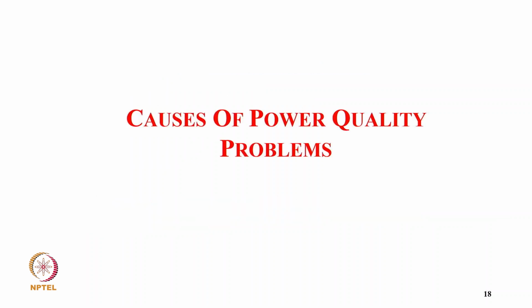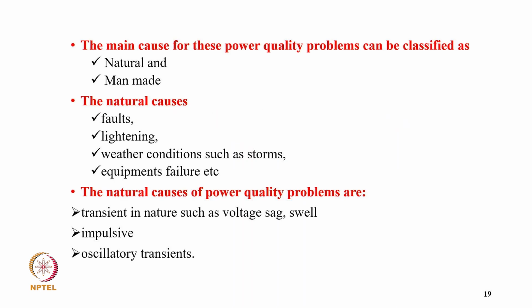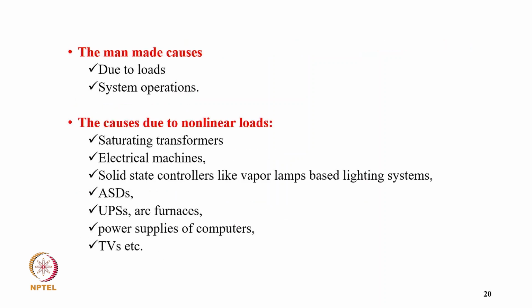Now coming to causes of power quality problems. The main causes can be classified as natural and man-made. The natural causes are fault, lightning, weather conditions such as storms, equipment failure, etc. The natural causes of power quality problems are transient in nature, such as voltage sag, swell, impulsive, and oscillating transients. And the man-made causes are due to loads and system operations, and the cause is due to nonlinear loads: saturating transformers, electrical machines, solid state control like vapor lamps, lighting systems, adjustable speed drives, UPS, arc furnaces, power supplies, computers, TVs.